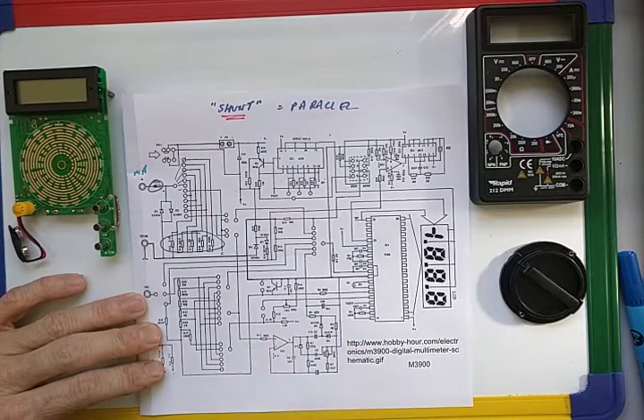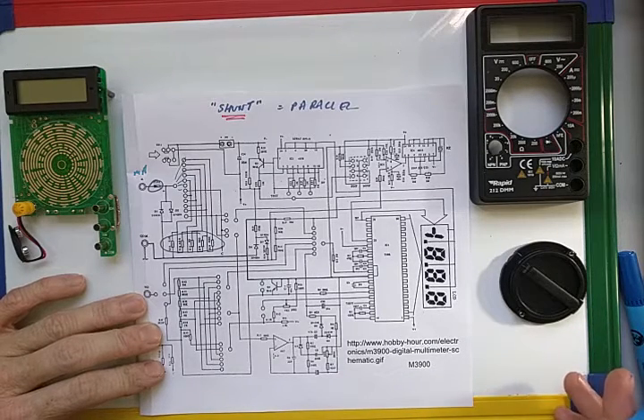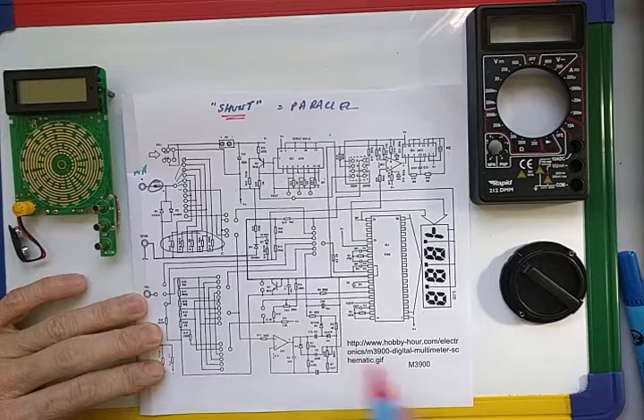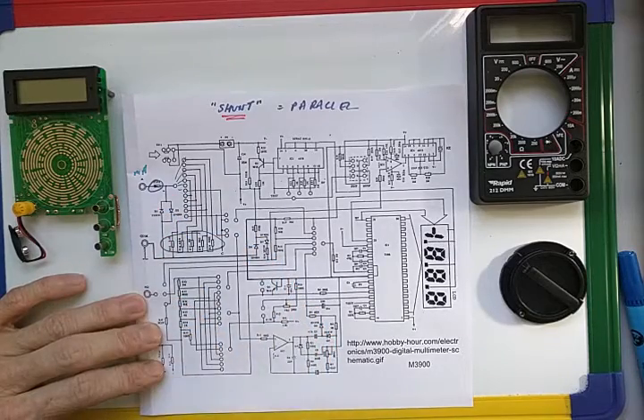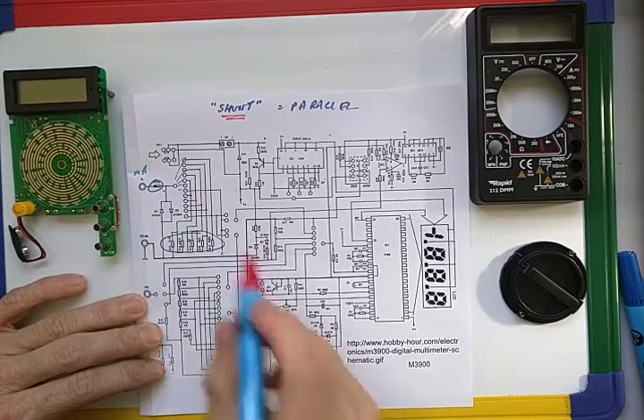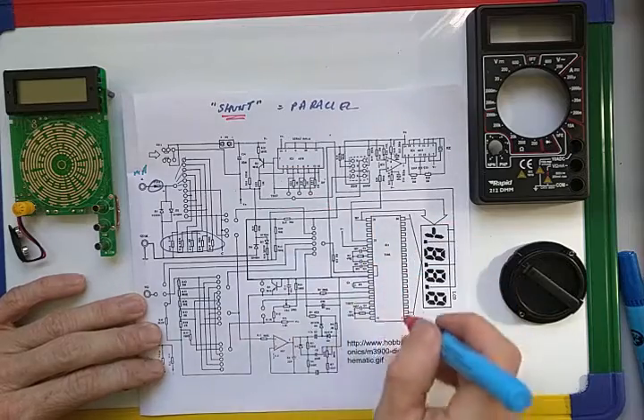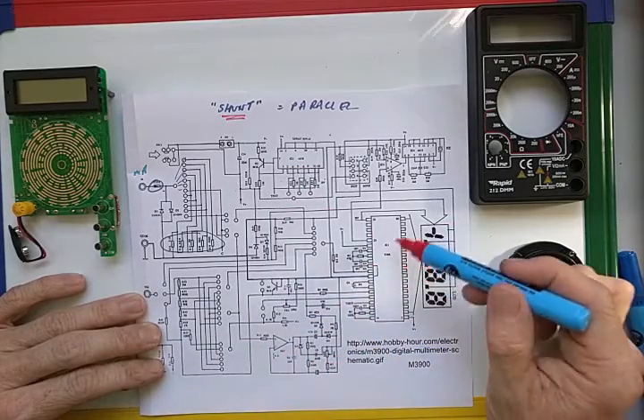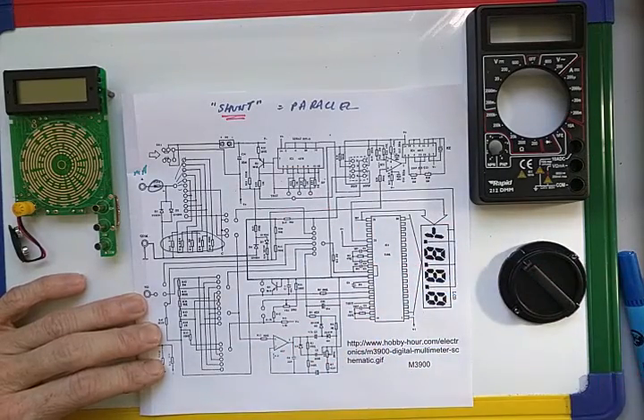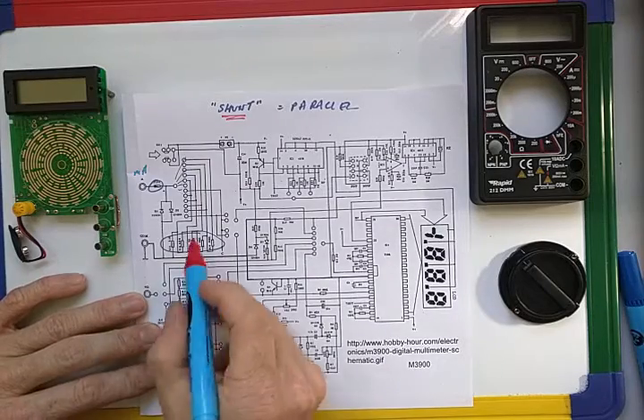So if you're measuring, let's say, 500 milliamps, what you find is that most of that 500 milliamps flows into the meter through a shunt resistor and straight back out and carries on, and a small fraction of it is fed into the meter, again because the main processor can only read these small voltages and currents.